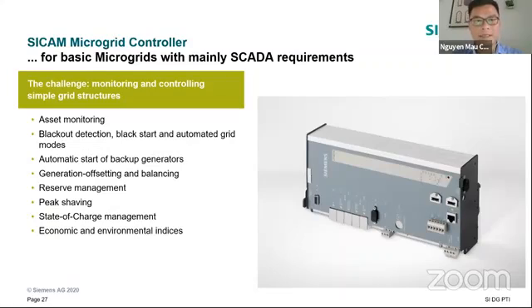MGC is a sort of microgrid controller, based on SICAM, and we apply this for very basic microgrids—let's say 1 solar, 1 battery, 1 diesel block, and load, so the configuration is simple. Then we can use CCAM, which can monitor access, monitor the PV panel, monitor transformer loading, automatically start the backup generator, handle reserve management, peak shaving, state of charge management for energy storage, and economic and environmental index.